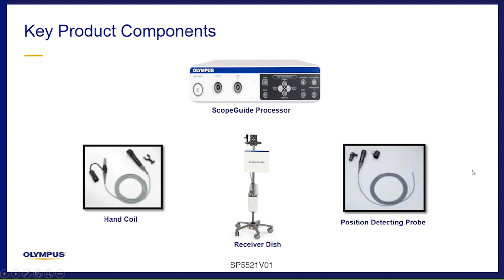This image on the right is called the Position Detecting Probe. This allows any of the older generation scopes, mainly the 180 series colonoscopes, to be made ScopeGuide compatible by passing this catheter through the biopsy channel, and that will then generate the electromagnetic pulses that will be picked up by the receiver dish. So that's also in addition if you have the older generation scopes.